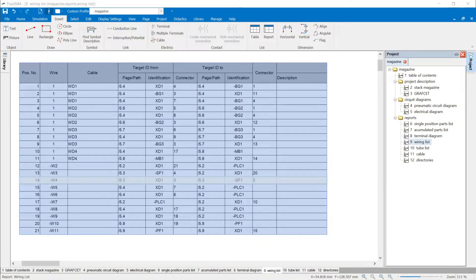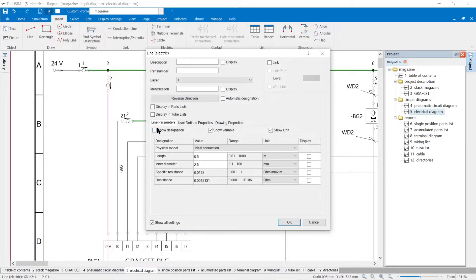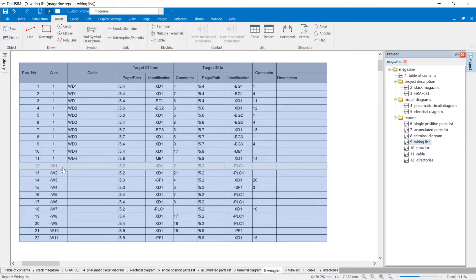Wiring Lists: The wiring list provides an overview of the electrical connections in the project. Electrical connections are the wiring lines in the control cabinet and the cables that connect the control cabinet to the sensors and actuators installed outside. Wires in the electrical circuit diagram are not automatically included in the wiring list. In the electrical circuit diagram, the properties of each line must be set. The line must be labeled and the checkmark for object display in tube lists must be set.